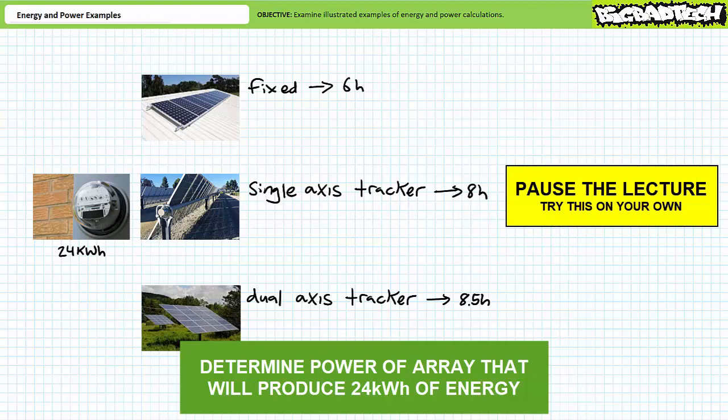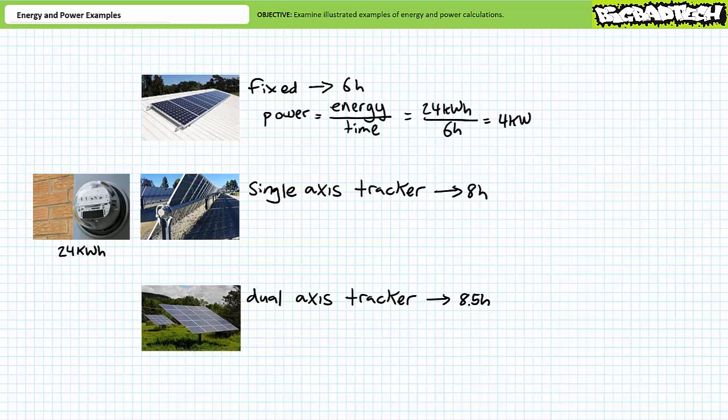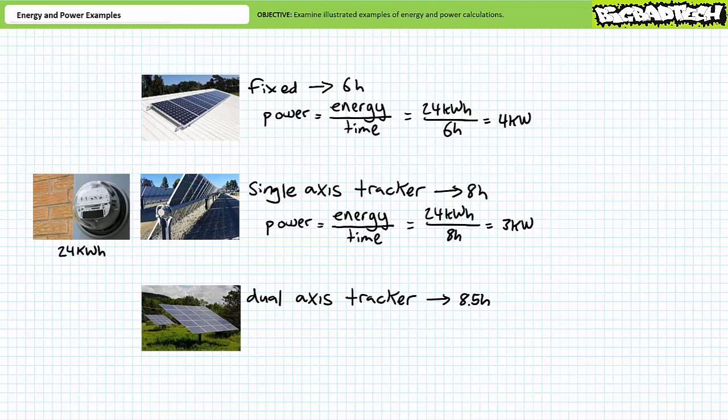By all means, pause the lecture and try this on your own. If energy is power times time, then power is energy over time. For the fixed stationary mount: 24 kilowatt hours over six hours demonstrates a 4,000 watt, or four kilowatt, solar array would provide the desired power rating. For the single axis tracker: 24 kilowatt hours over eight hours demonstrates a 3,000 watt, or three kilowatt, solar array. For the dual axis tracker: 24 kilowatt hours over 8.5 hours demonstrates a 2,823.5 watt, or roughly 2.8 kilowatt, solar array.